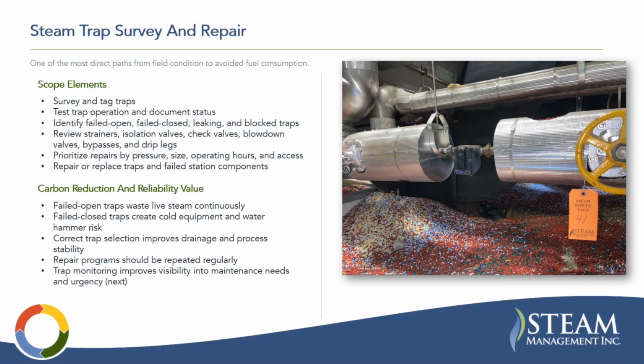You're going to prioritize repairs by pressure, size, operating hours, and access if you're not going to be able to repair all of the failed traps. And then you're going to repair or replace traps and failed station components. The carbon reduction and reliability value: failed open traps waste live steam continuously. And traps are generally designed to fail open so that the condensate still can get out of the system to avoid hazardous conditions and so the equipment can still operate properly.